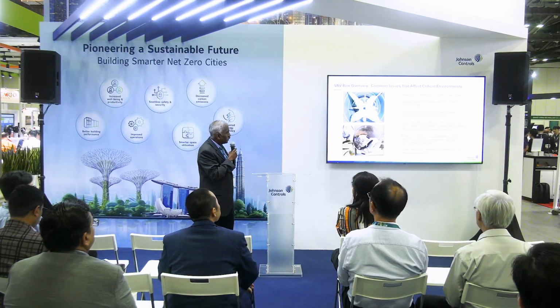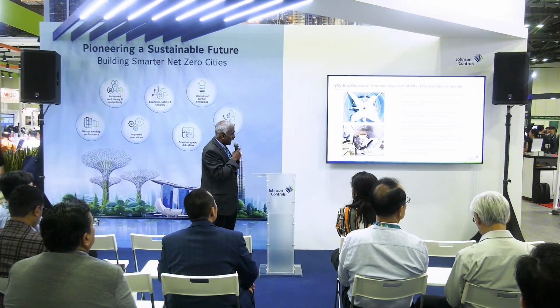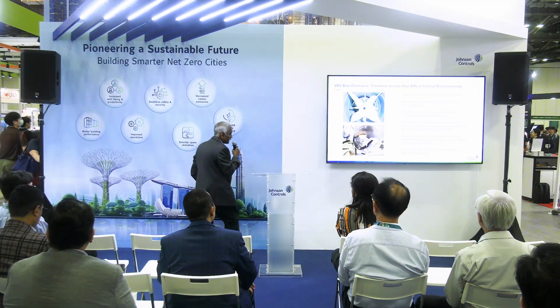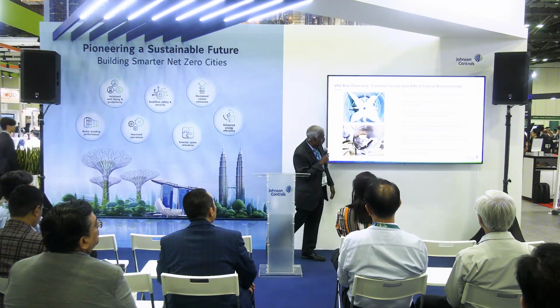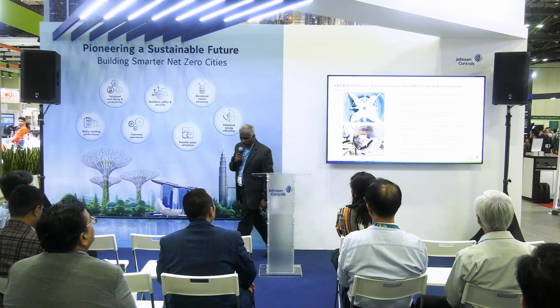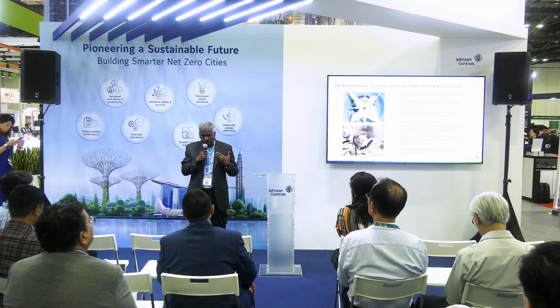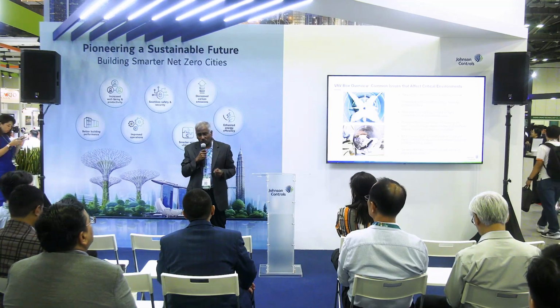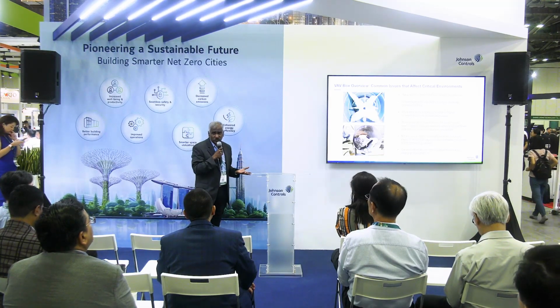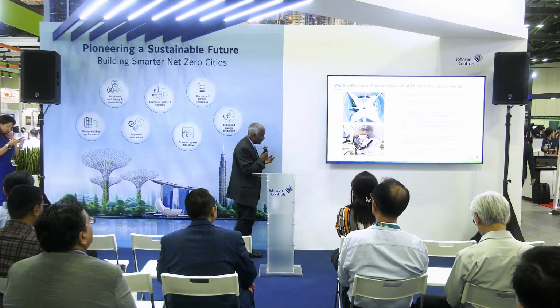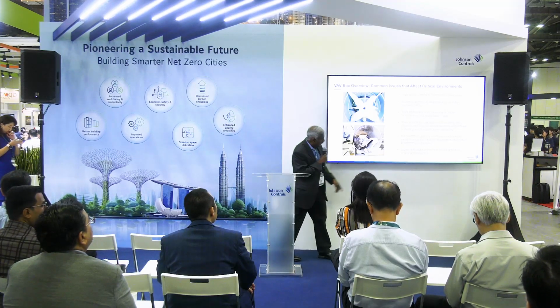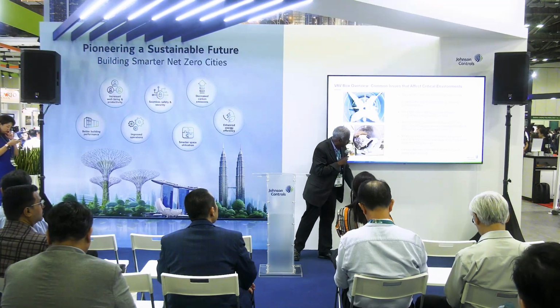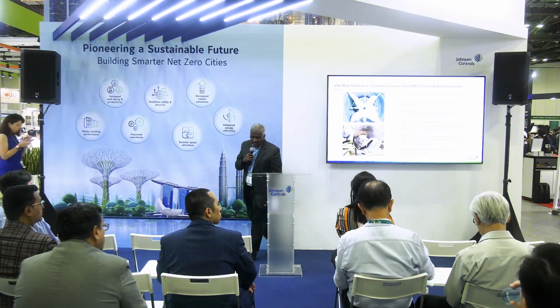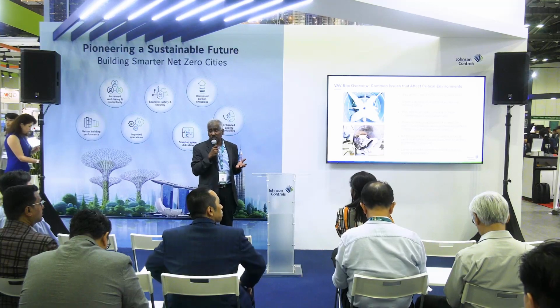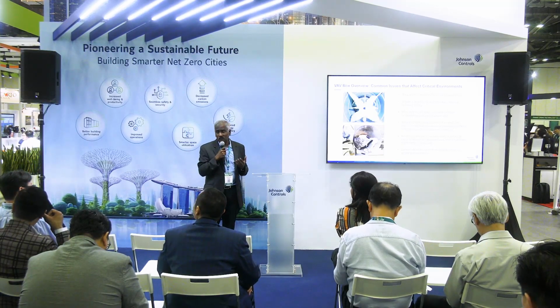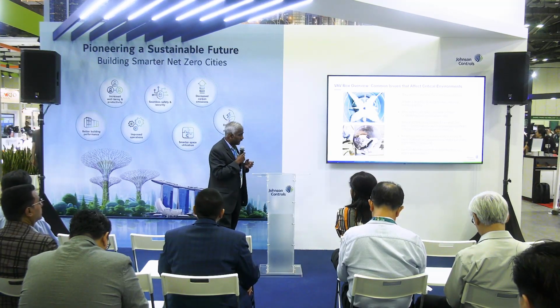Then there are strict guidelines on protocols for cleaning, so again we need to have a time for all of that. And it's not precise control, especially when it comes to rapid changes. What do I mean by rapid changes? As I was saying, like opening a door, or someone opens the toilet door, so you need to respond very fast. These are some of the challenges faced when using the VAV, which cannot effectively control directional airflow. I think it's okay to use for normal consulting offices for healthcare, but not for critical operation areas or critical areas.